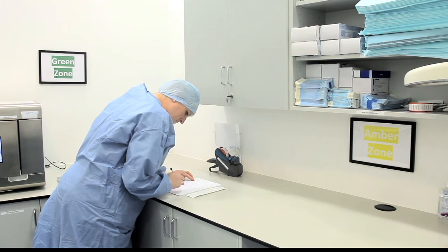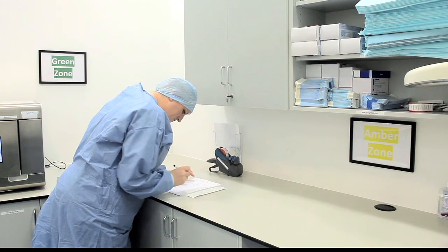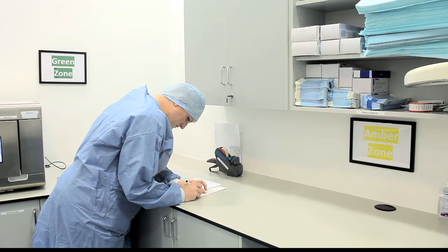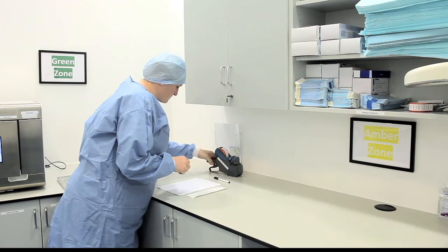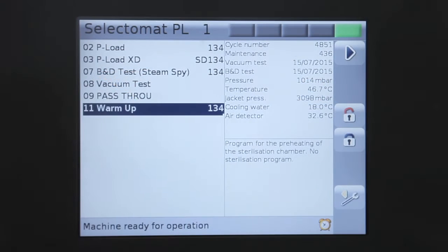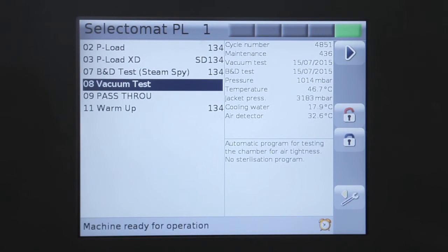The warm-up cycle graph printout should be signed and documented. When the cycle is complete, it is important to check the graph printout before moving on to the next test. The second test to be completed is the vacuum leak rate test. This test is carried out on a weekly basis to detect air leakage in the autoclave chamber. It is recommended to perform this test on the first working day of the week. Air leaks can result in wet packs, as leaks may affect the drying process. Furthermore, the presence of air in the chamber prevents steam penetration of the load and can prevent sterilisation.